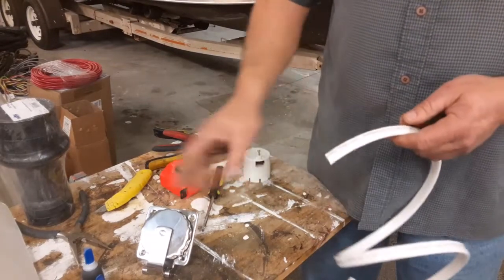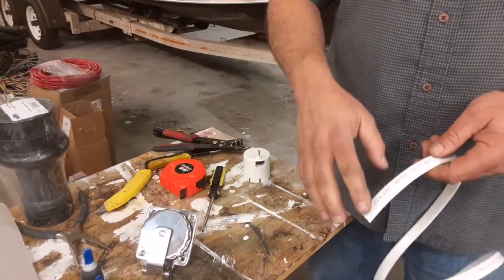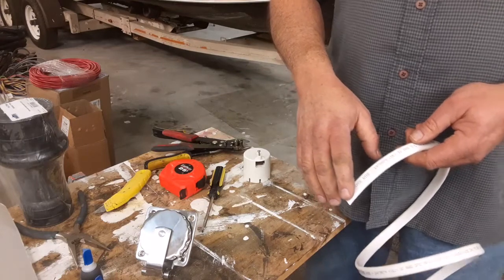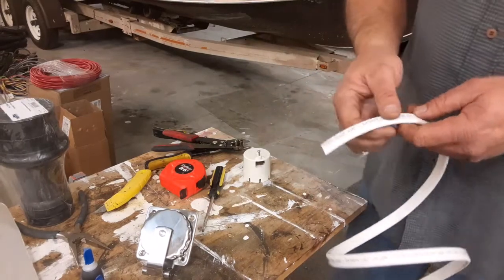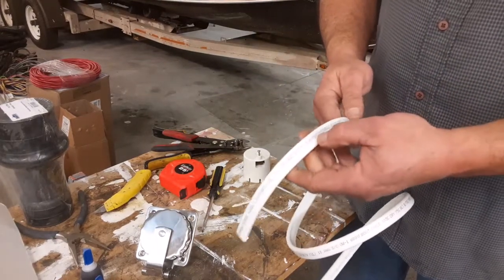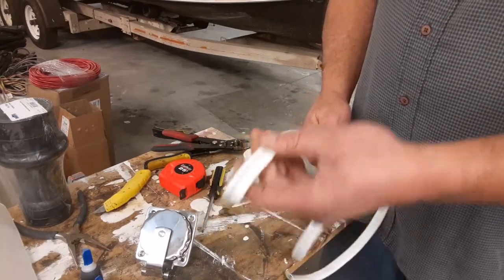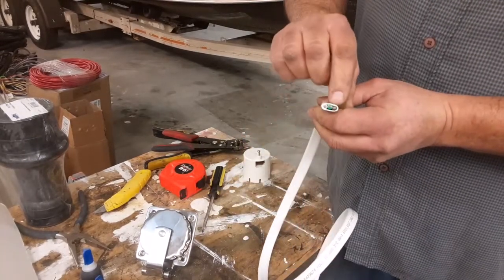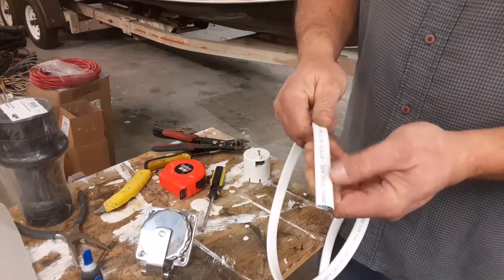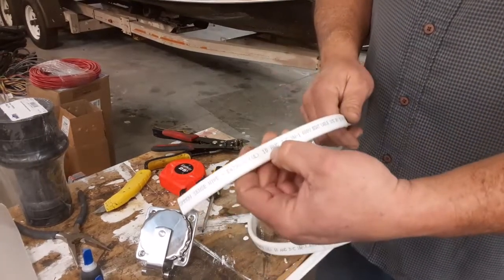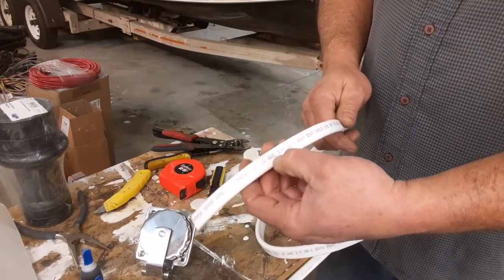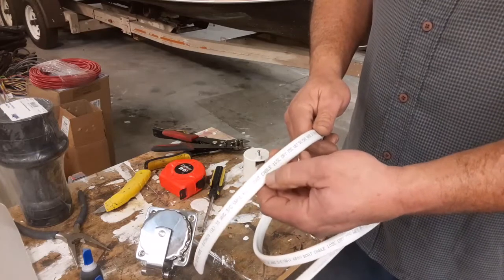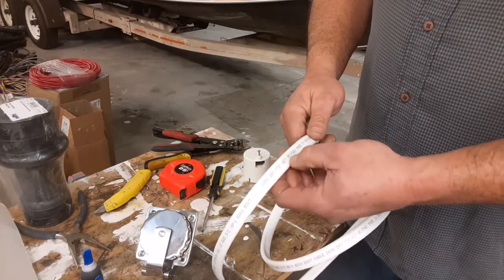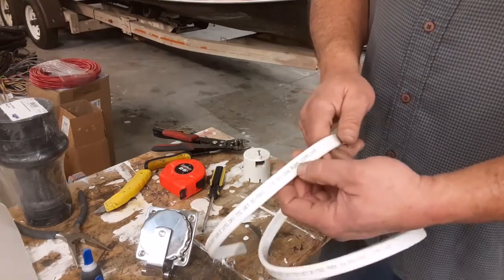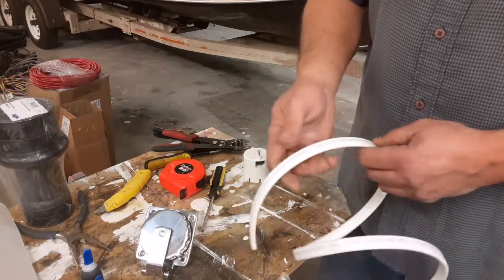A 30 amp service from the weatherhead to the circuit breaker box, or fuse box, is going to require 10 gauge wire. As you can see, we have three conductors: power, ground, and neutral. The wire is rated 10 AWG ABYC for its gauge. It's also identified as boat cable. It can be used in wet places, and it's made in the good old US of A.